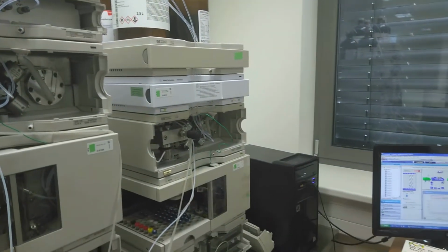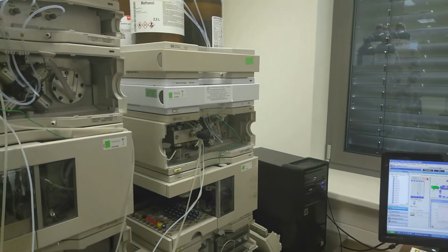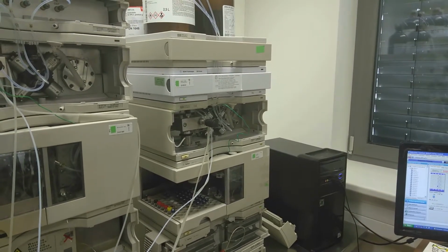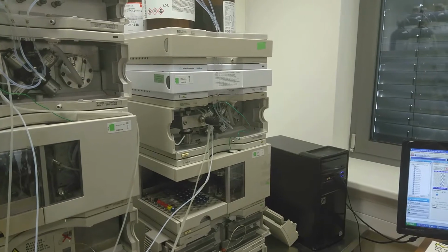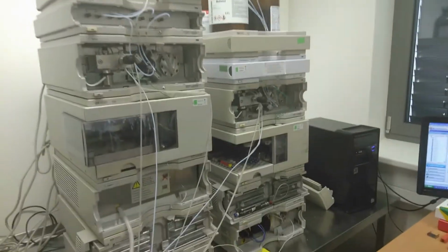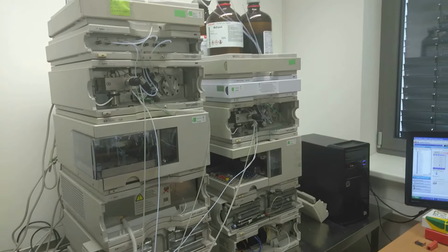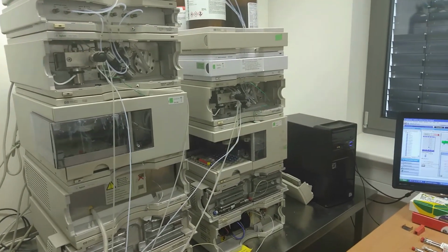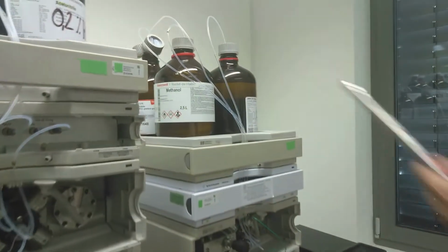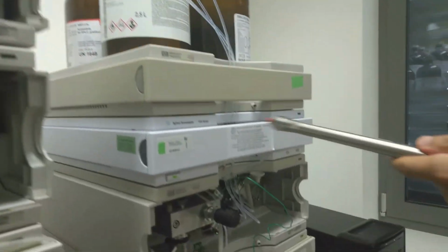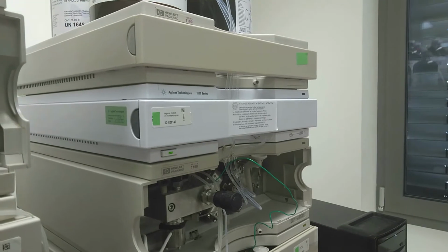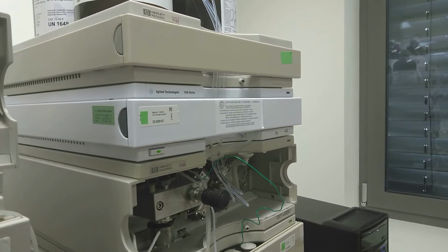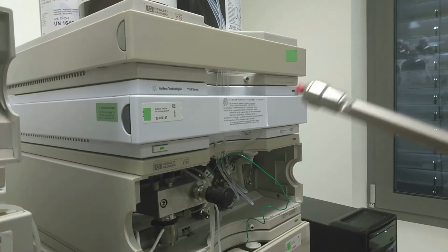Here you can see the typical arrangement of a system for analytical HPLC. The system is usually composed of several modules which are separately remoted from a driving computer.